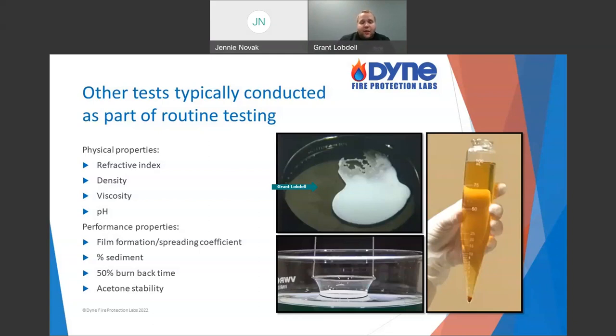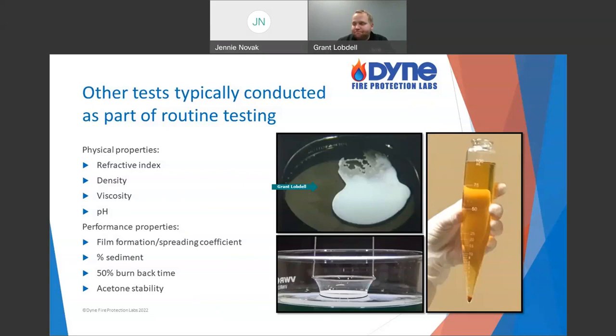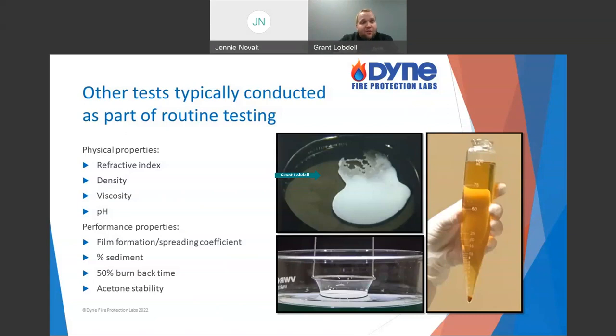There are a couple of ways to test film formation. We can take a Petri dish, put cyclohexane in it — cyclohexane is referenced right from NFPA and IMO standards, it's a fuel that's been standardized across the industry because gas varies throughout the world and year to year, which isn't uniform enough for lab testing. We put some foam solution on the cyclohexane and see if we can see that translucent film. You can even light a match over it. If it forms a film, that confirms it's a film-forming foam.